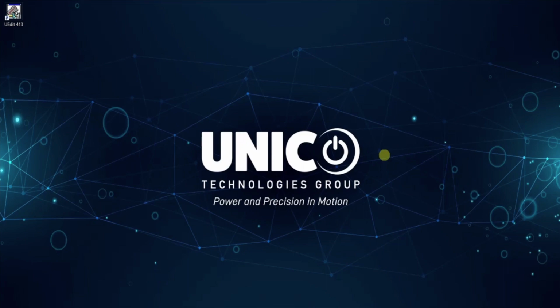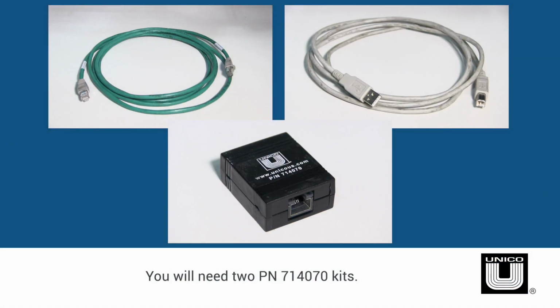326756, and the DCR5 module, part number 329039. Communication to the DSP module will be necessary to control the drive through UEdit and perform the flux mapping process. Communication to the DCR5 module will be necessary to extract the flux mapping results and analyze the data. For this, you will need two different sets of Unico serial communication kits, part number 714070.